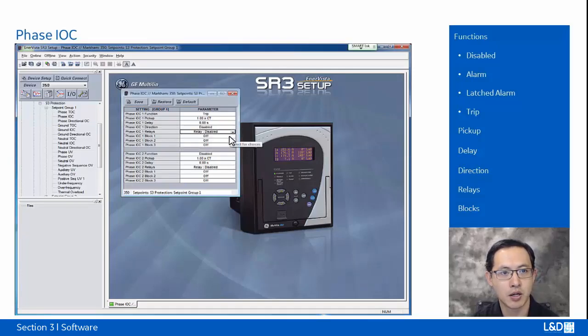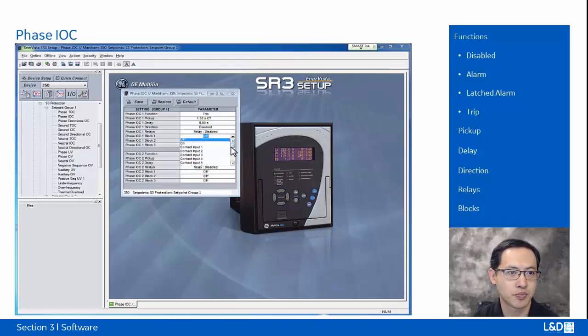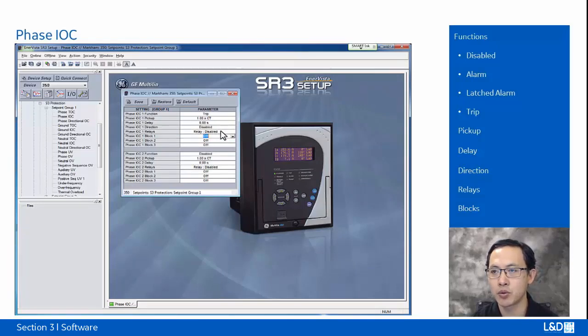And this function can also be blocked by 3 inputs, block 1, 2, 3, and under each input we can select contact inputs, virtual inputs, logic inputs, remote inputs, and other conditions. And these are common settings in the Phase IOC, but they are applicable to all the protection elements.